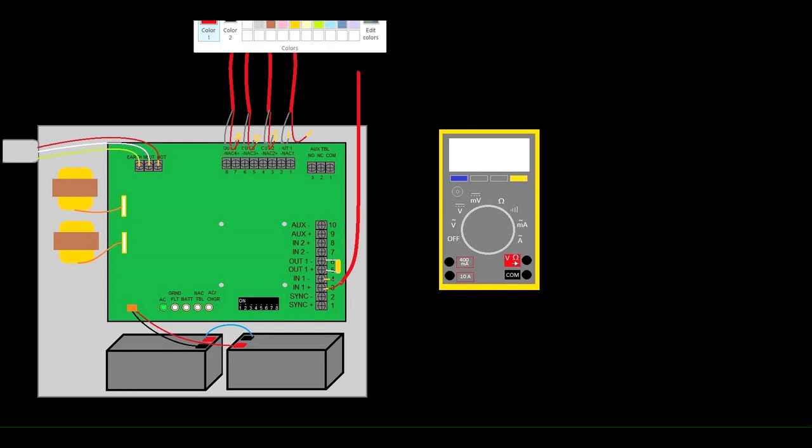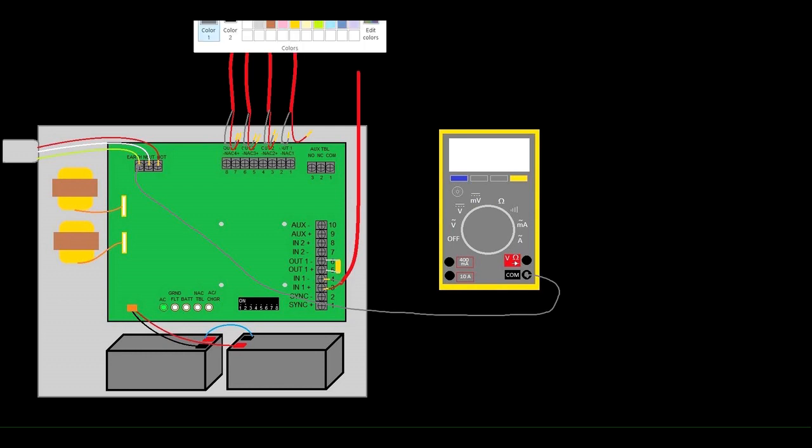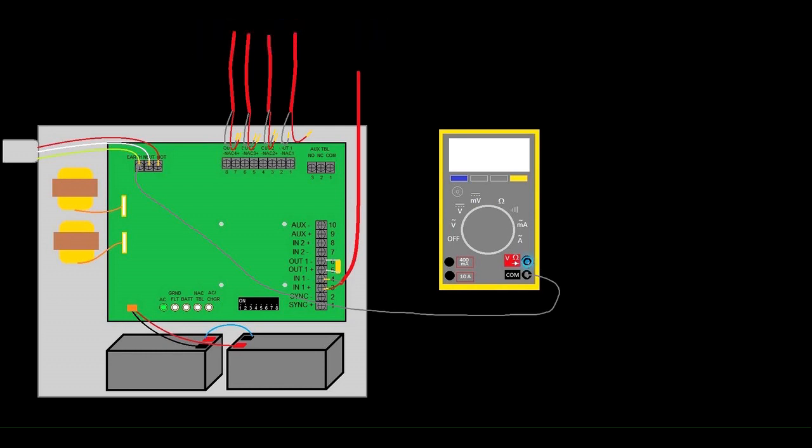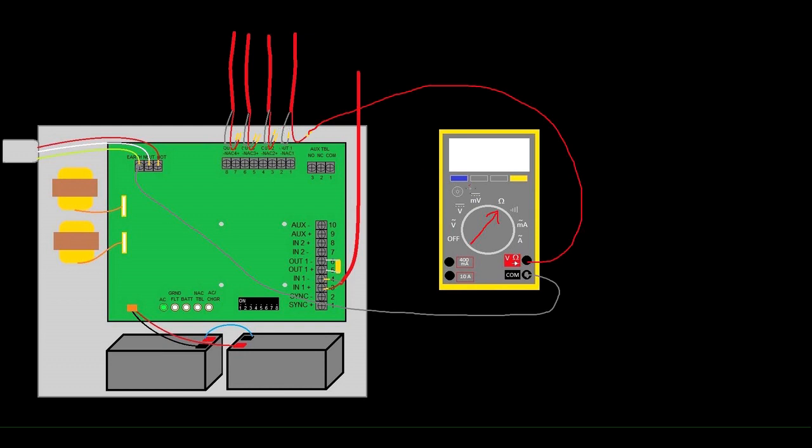So the first thing we're going to do is take one leg of our meter, doesn't matter which one, and we're going to go to earth ground. We'll take our negative and go there, and then we'll take our positive leg of the meter and start going one by one to each leg of these outputs, these NAC circuits. We know that these are not going to have voltage on them unless somebody really screwed up in the field, so we're comfortable setting our meter to resistance. There's a whole range of readings you could get here, and it's important that you understand what those readings mean. That's kind of the point to some of these videos.